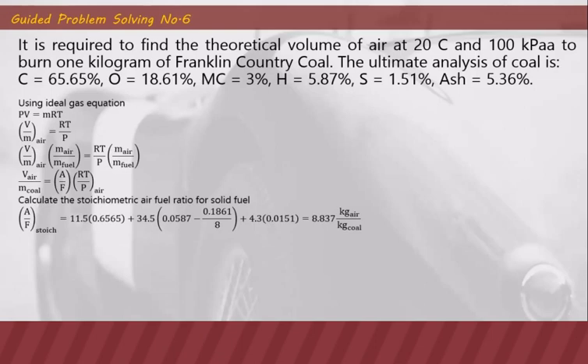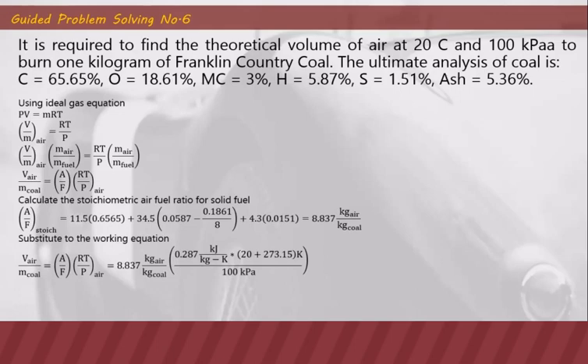We first calculate the stoichiometric air-fuel ratio for the solid fuel, which is 8.837 kg-air per kg-coal. Substituting into the formula along with the gas constant of air (0.287 kJ/kg·K), the temperature converted to Kelvin (293 K), and the pressure of 100 kPa absolute, we obtain the theoretical volume of air as 7.43 cubic meters of air per kilogram of coal.